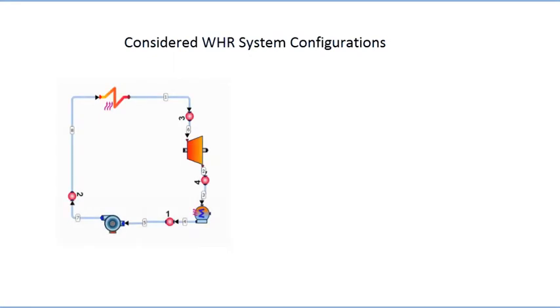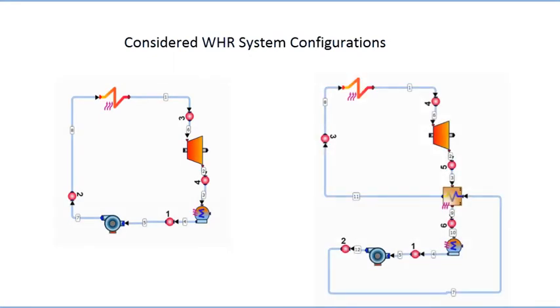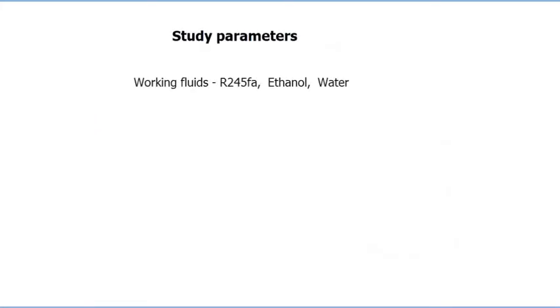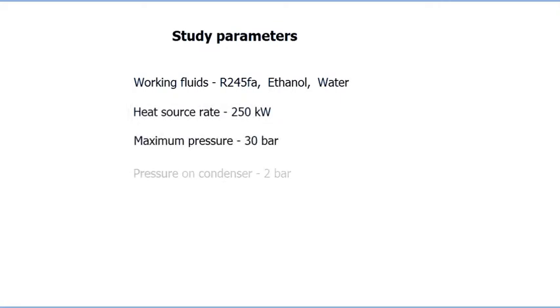Two configurations will be considered in the current study: a simple Rankine cycle and a Rankine cycle with recuperation. The goal is to determine the working range of operational parameters — pressure and temperature — for both configurations, using working fluids R245fa, ethanol, and water steam. The heat rate of the heat source is 250 kilowatts. Due to design constraints, maximum pressure is limited to 30 bar and pressure on the condenser inlet is 2 bar.